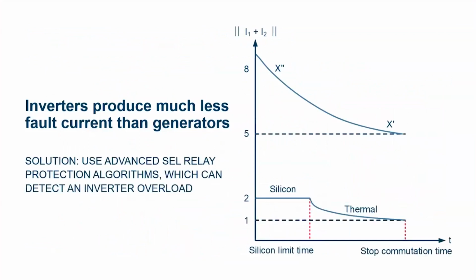Inverters also produce a lot less fault current than your conventional synchronous generators, a lot less current transiently. And here, in this XY plot, I'm showing that the X double prime is the subtransient reactance that we mathematically simplify from a flux-induced event in the air gap of a generator. It's a number. And on average, this parameter that we have known for over 100 years is that a synchronous generator produces about 8 times its rated current during a fault, momentarily, then falls off to somewhere around 5 times its rated current during a fault. This is what we call the subtransient and transient reactance effect. Well, inverters don't do that. And that is a paradigm shift.